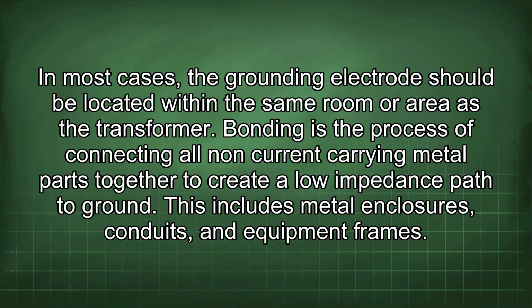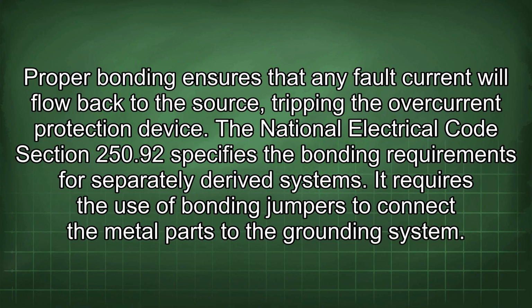Bonding is the process of connecting all non-current carrying metal parts together to create a low impedance path to ground. This includes metal enclosures, conduits, and equipment frames. Proper bonding ensures that any fault current will flow back to the source, tripping the overcurrent protection device.